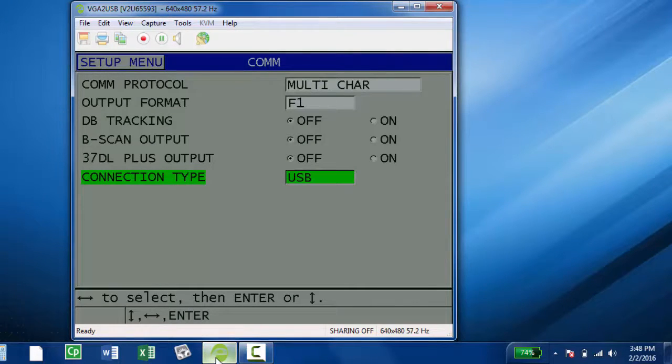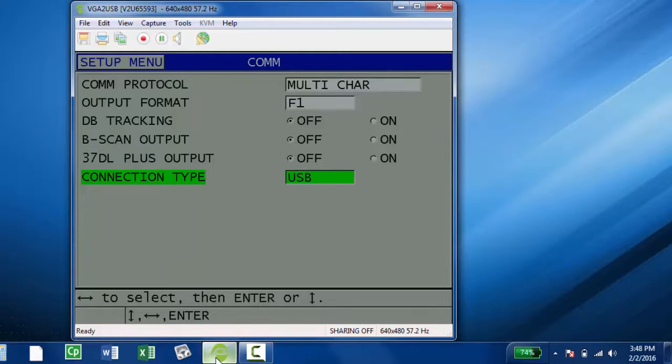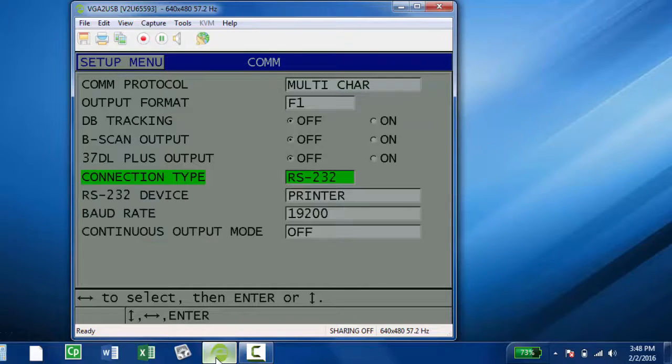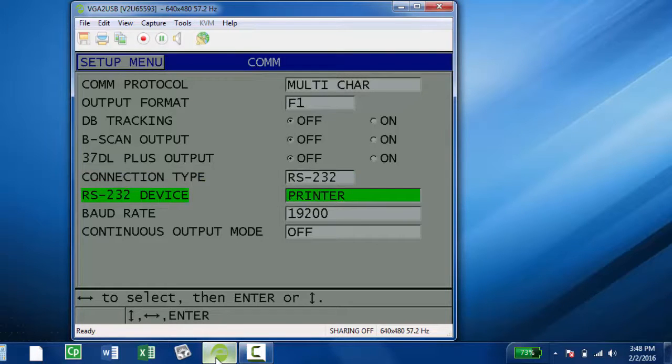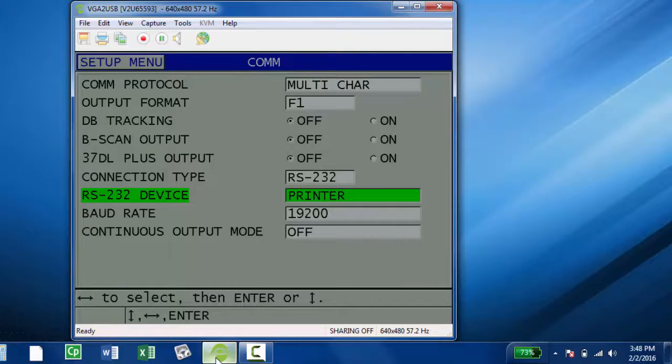We're connecting through an RS-232 cable, so you want to make sure that the connection type is set to RS-232. Right now it's showing USB. Use the right arrow and switch that to RS-232, then switch the RS-232 device to Terminal using the right arrow.